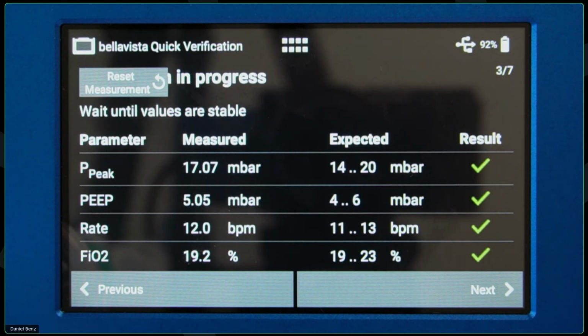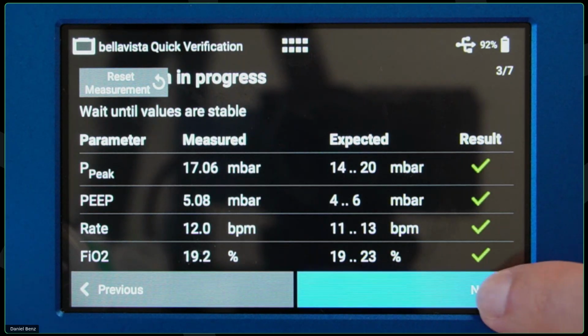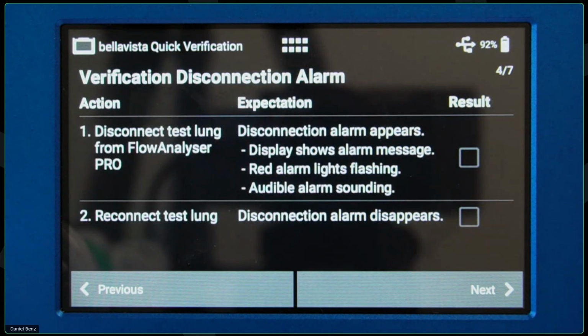In such cases, the software does that automatically for you because we have the measurement and we know the calculation. So the app already does that for you, shows you the expected range based on your actual measurements, and shows you the result right on the screen. If I click next here, it locks all these measurements in. And then sometimes, you know that from annual preventive maintenance procedures and performance verifications, it's just testing something and then confirming that that happens.